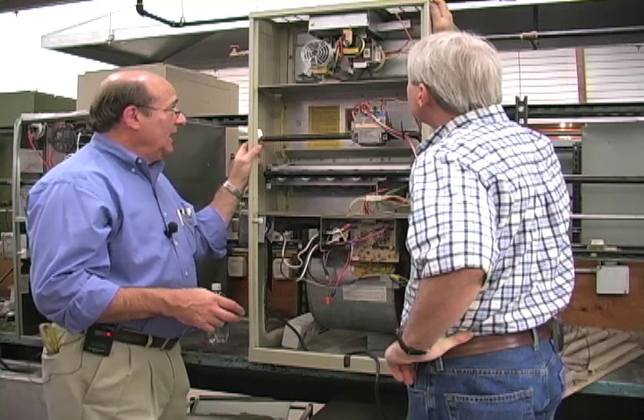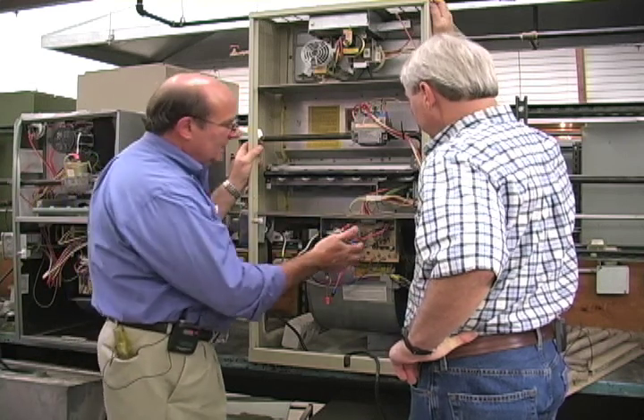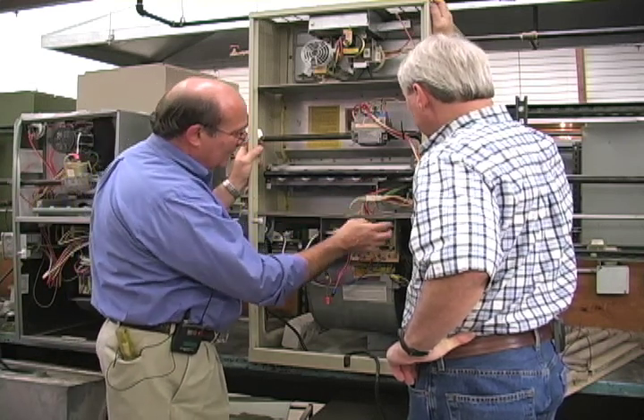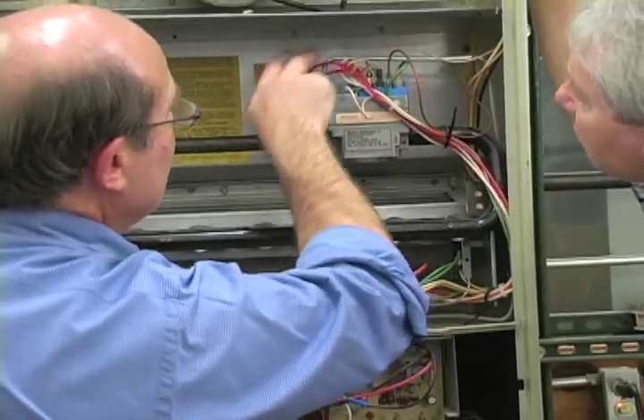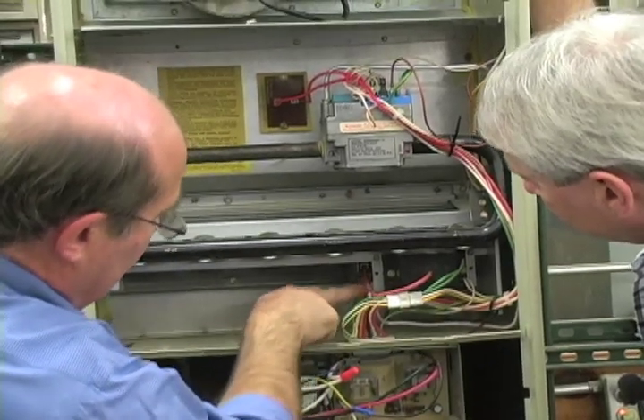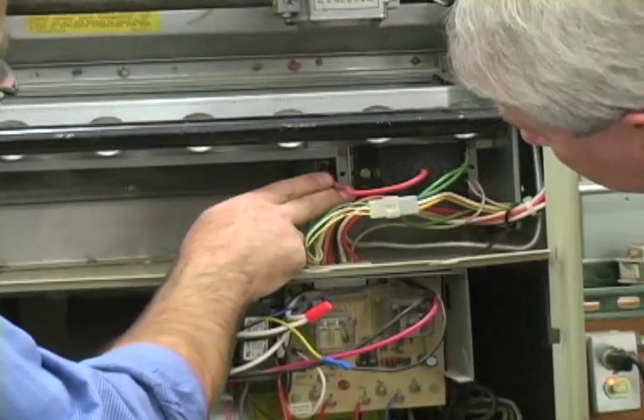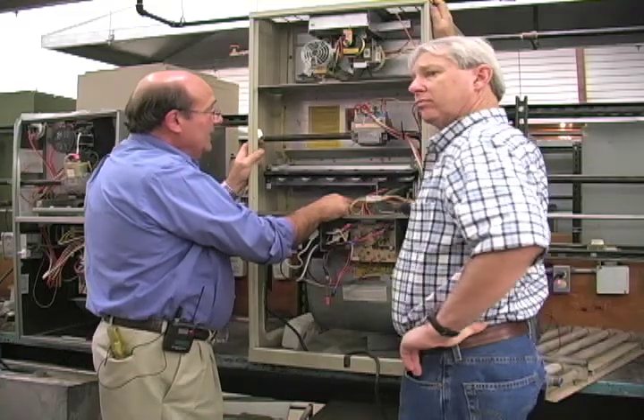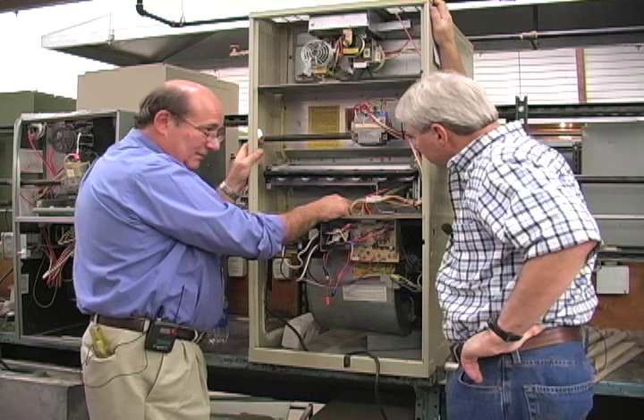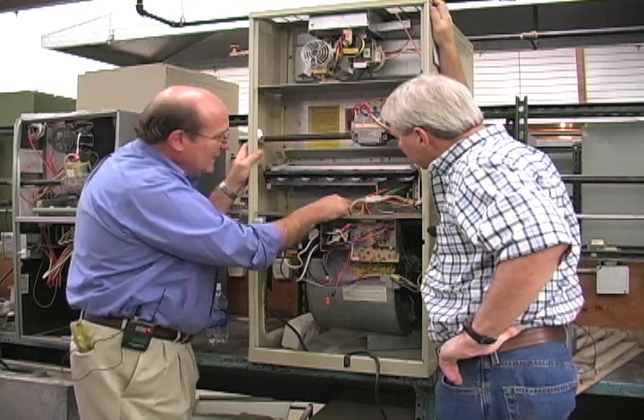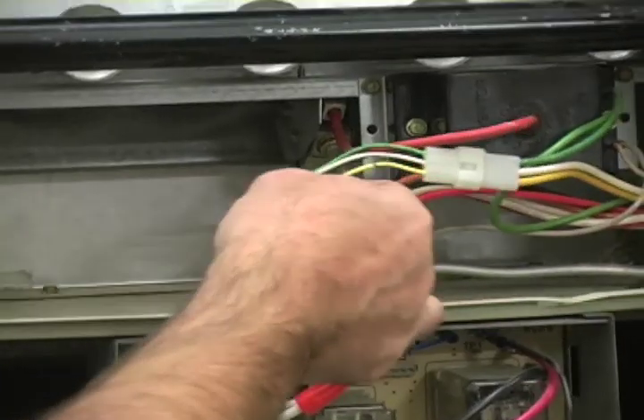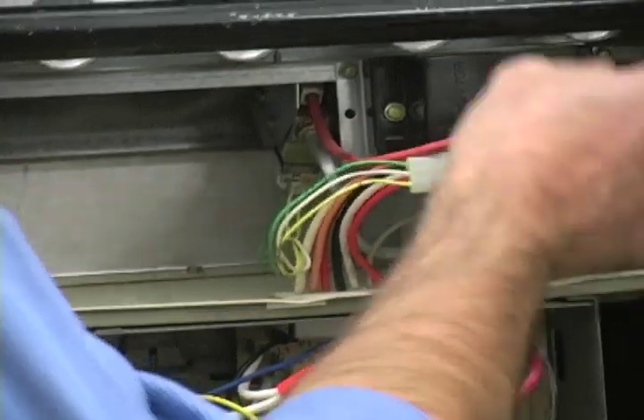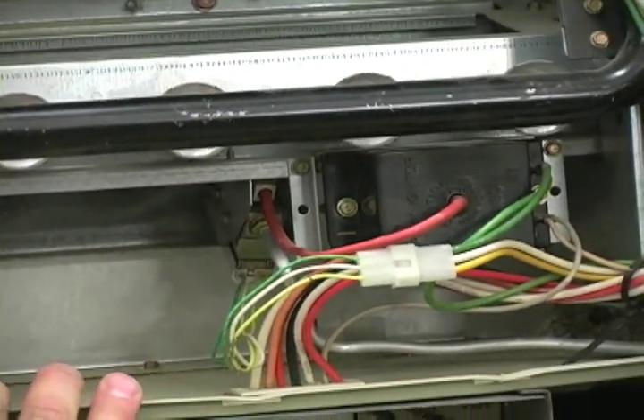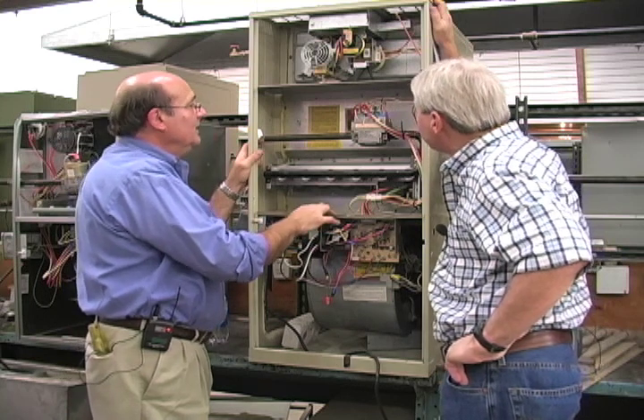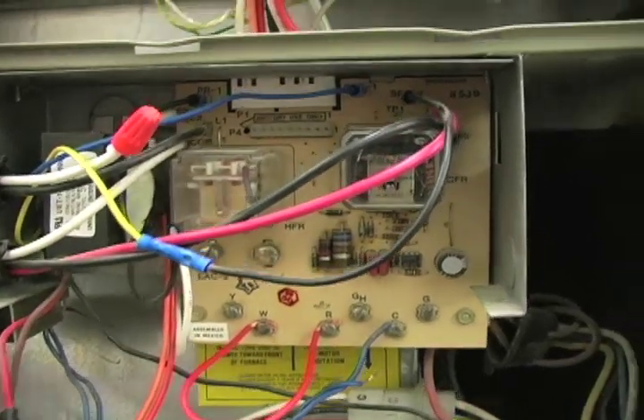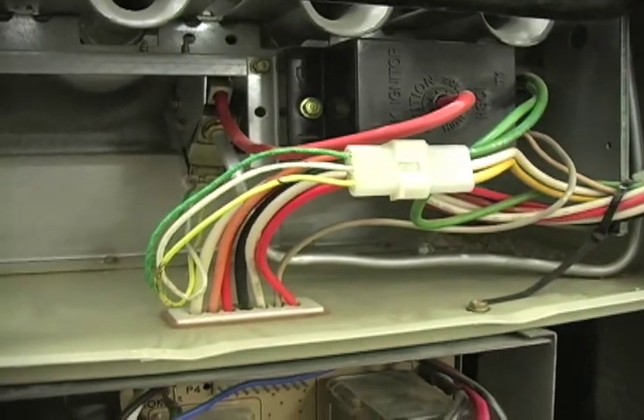And then after we go through the purge cycle, the igniter circuit will come on, and it'll open up the pilot gas valve over through here, and this safety valve is the pilot line over here. It comes down into the pilot valve over here with the electronic igniter right next to it, and then the pilot will come on and we'll initiate a pilot flame. Once the pilot flame is initiated, there's a flame sensor, which is a safety control. It's this device here, and that tells the main gas valve that we've got a good pilot and we're ready to open up that gas valve. So those are the primary features of an 85% furnace: intermittent pilot, inducer blower motor.